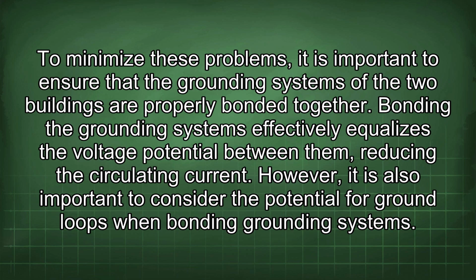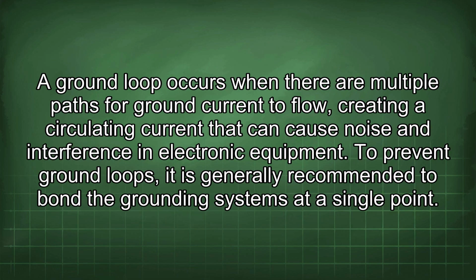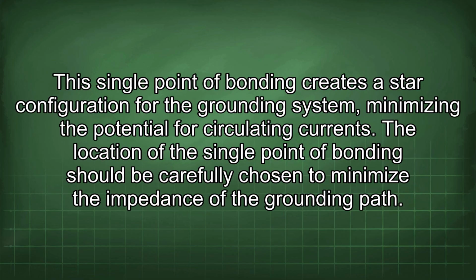However, it is also important to consider the potential for ground loops when bonding grounding systems. A ground loop occurs when there are multiple paths for ground current to flow, creating a circulating current that can cause noise and interference in electronic equipment. To prevent ground loops, it is generally recommended to bond the grounding systems at a single point. This single point of bonding creates a star configuration for the grounding system, minimizing the potential for circulating currents.